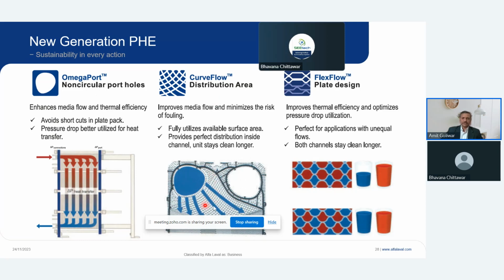Similarly, the distribution pattern, wherein if you see, this is the shorter distance, and this is a longer distance. So fluid which comes into the plate area takes more time, or the pressure drop for reaching a farther location is high compared to the shorter distance. Because of this, we have observed that any plate heat exchanger will have more choking and scale formation problems on the farther side of a plate, of a port. So there are heat exchangers where you can have this distribution area equal, and the pressure drop is equally managed.